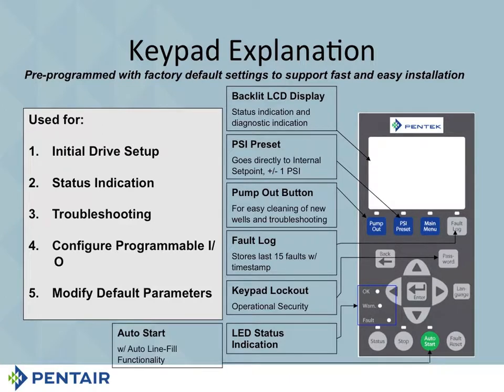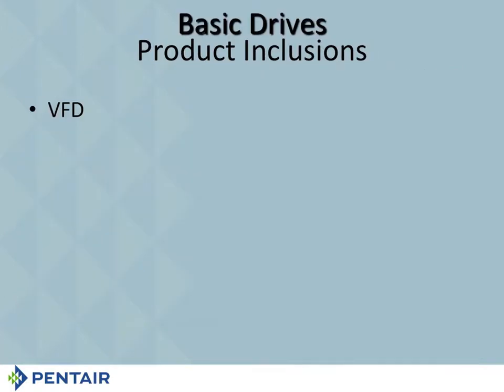There is also an auto start. Now you'll notice it says auto start also has auto line fill functionality with it, and we'll explain what that is. There's also those little rectangular lights above status, stop, and auto start. They'll be on too, letting you know where you are. Okay? Now, the basic product that you're going to get here, you're going to get the variable frequency drive.